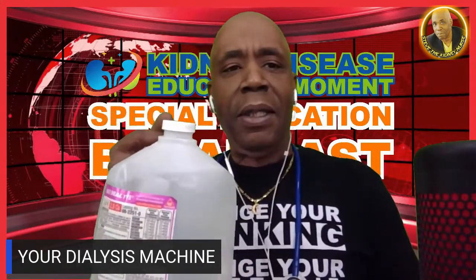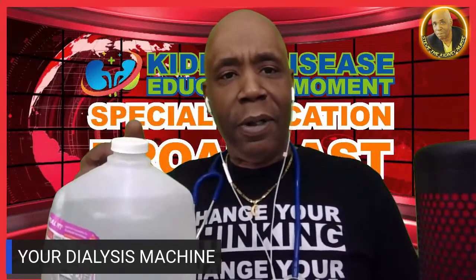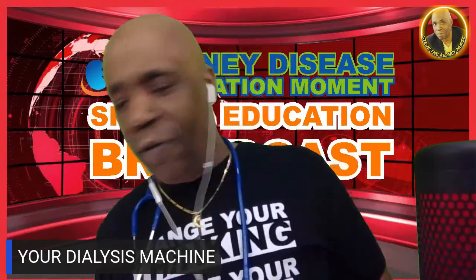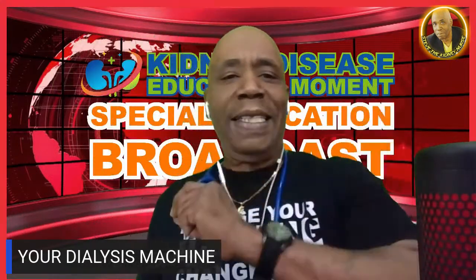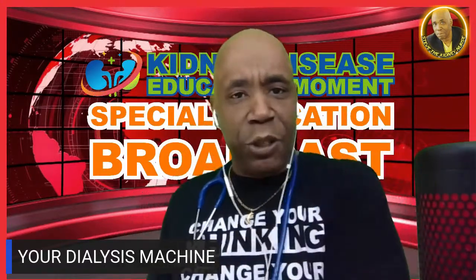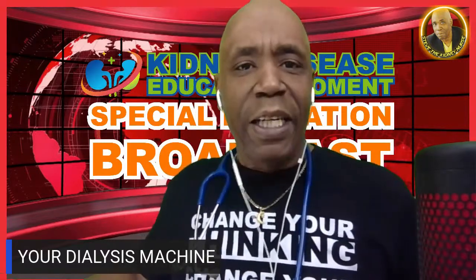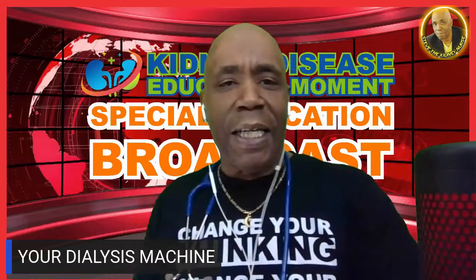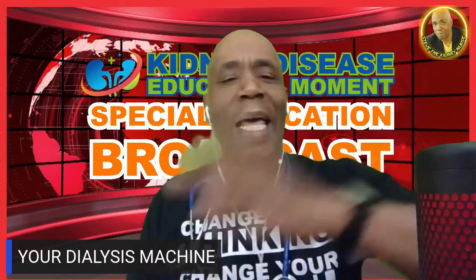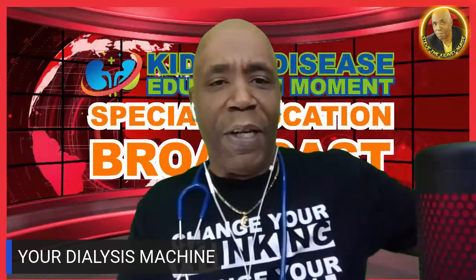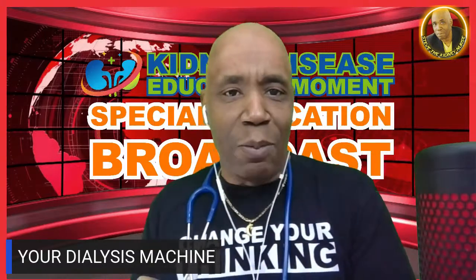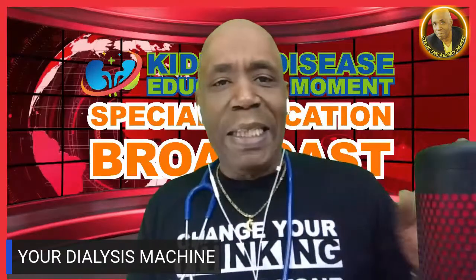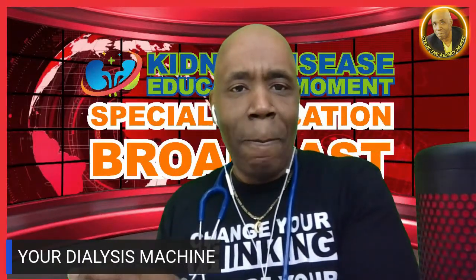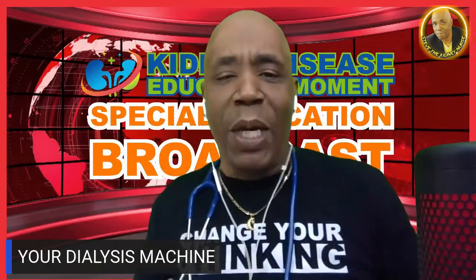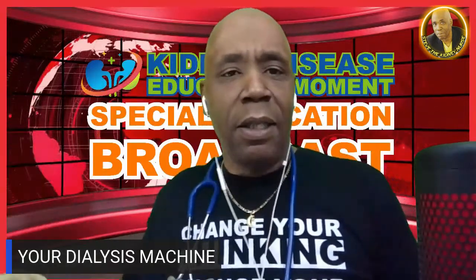And sometimes what happens, if this runs low and the machine goes into low conductivity, the longer they take to resolve that issue, meaning the staff go and get another bath and change it, now the machine has to come up and correct itself and get back into conductivity. All that time that the machine says low conductivity, that stops your treatment time. Anytime the machine stops, it stops the treatment time, meaning your treatment is still running, but the UF stops.